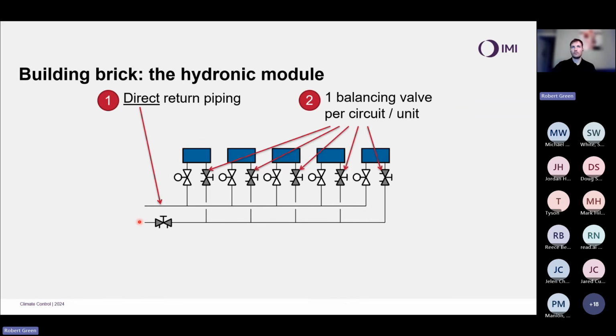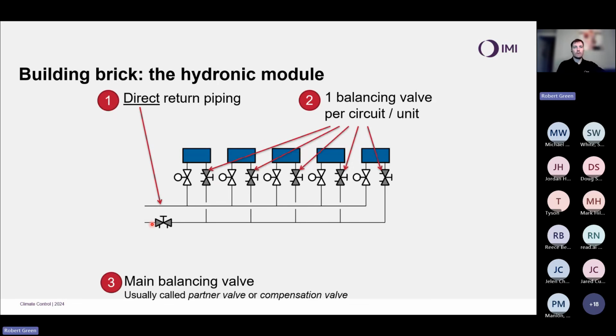We must have direct return piping to exploit that proportional rule. If we run what's called reverse return, which is often used, and in our full courses we show why reverse return doesn't work, headline figure, it's not a great solution, we would not be able to exploit that proportional rule. And finally, we want to have a main balancing valve called a partner valve or compensation valve. And we're going to see in this hydronic module setup why this valve is really important, because this is going to have a real purpose there.